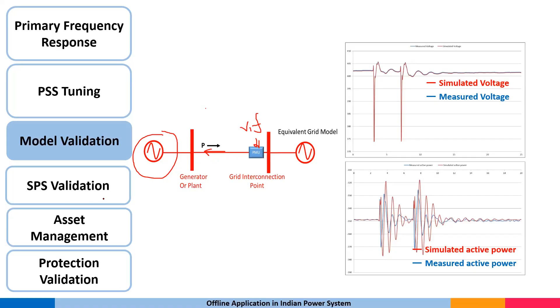We have a large number of protection schemes in the system. As already told, we can use this synchrophasor dynamic information to check whether the protection scheme is acting properly or not. Let us say I have a protection scheme where we are measuring two powers from two transmission lines. We are summing them, and if the sum is more than 1500 megawatt, let us say for 2.5 seconds, then an action has to be done. If it is less than that, then no action is required. So what we see is that one SPS has operated during this time. Whether it was a correct operation or not? The summation from the line is measured by a device located in the field.